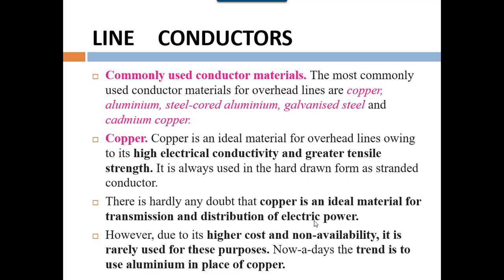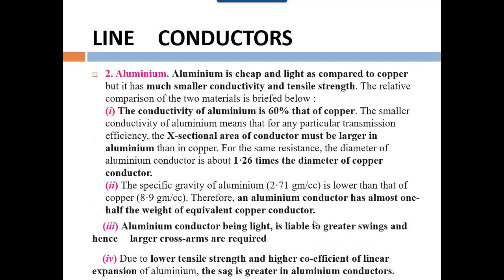There are different types of conductors used in transmission lines: copper, aluminium, steel-core aluminium (ACSR), galvanized steel, and cadmium copper. Copper is an ideal material — when pure, its electrical conduction is outstanding and it is the best conductor available. However, its availability is limited and its cost is very high, so copper is used for short distances. For long distances, aluminium wire is preferred. Aluminium is comparatively cheap and its weight is less than copper, but its conductivity is about 60% that of copper.